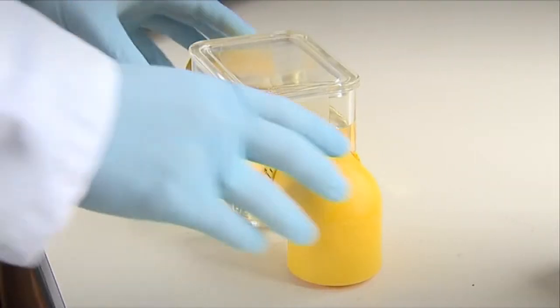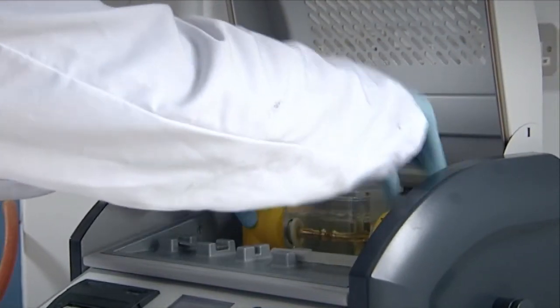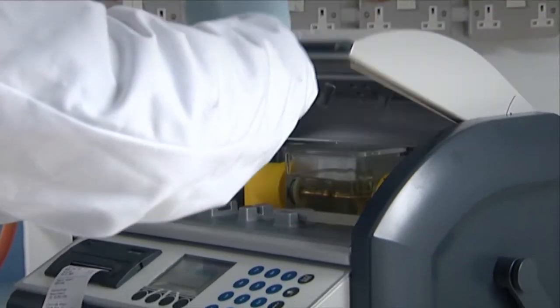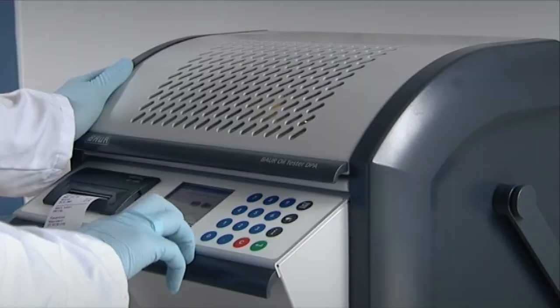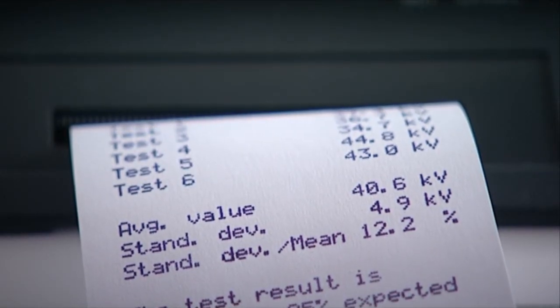The last test that's run is the electrical breakdown strength, and this is the voltage at which you get a breakdown of the oil across two electrodes. The dielectric breakdown strength of the oil is very dependent on the level of water and the level of solid contamination in the oil.